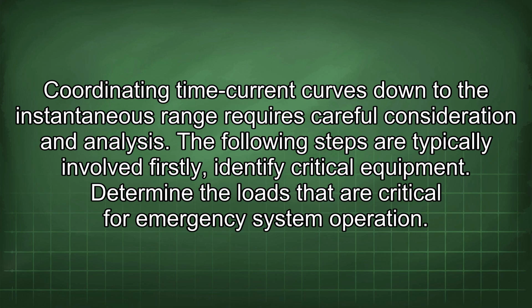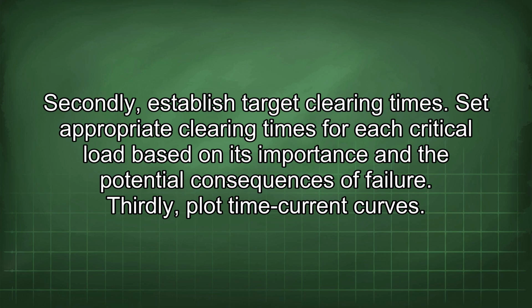Coordinating time current curves down to the instantaneous range requires careful consideration and analysis. The following steps are typically involved. Firstly, identify critical equipment. Determine the loads that are critical for emergency system operation. Secondly, establish target clearing times. Set appropriate clearing times for each critical load based on its importance and the potential consequences of failure.